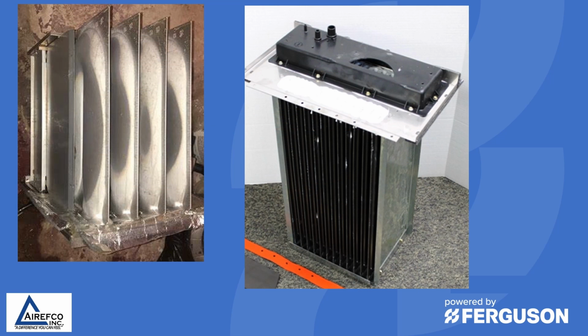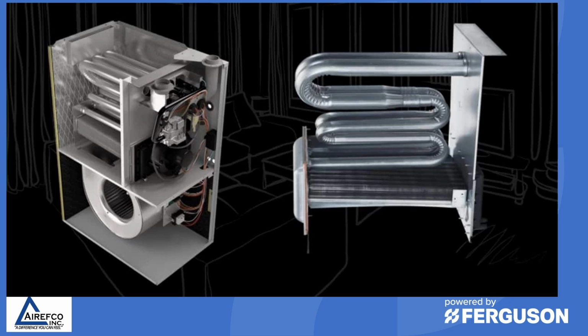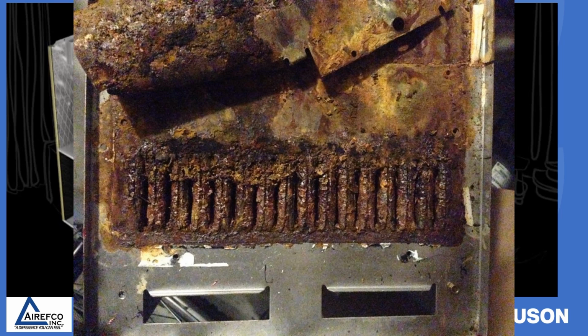So here you see the heat exchangers of a modern gas furnace. On the left you see the primary cells that should be examined for holes and cracks. On the right you see the secondary heat exchanger, which you would find in a 90% furnace to extract more heat out of the air as it passes across the heat exchanger. These heat exchangers, like I said, need to be examined periodically, and definitely before each heating season you should double check the heat exchangers for any cracks or holes to make sure that they are operating correctly. This, of course, is a totally corroded heat exchanger, and if you find something like this, you definitely need to replace it.